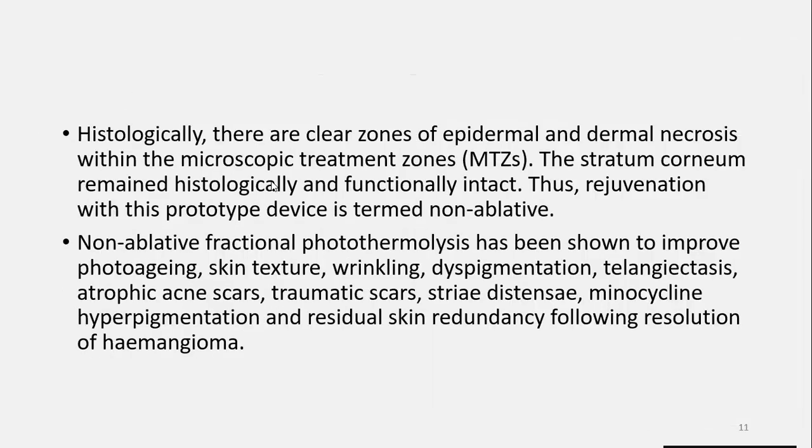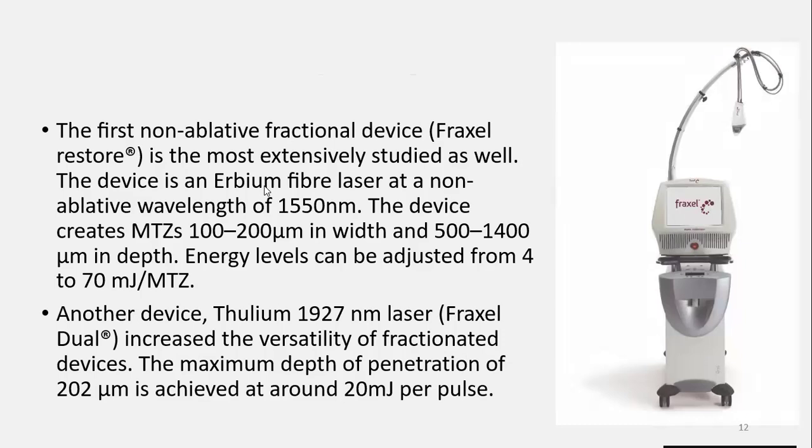These devices create microscopic treatment zones ranging 100 to 200 micrometers in width and 500 to 1400 micrometers in depth. Energy levels can be adjusted from 4 to 70 millijoules per microscopic treatment zone.